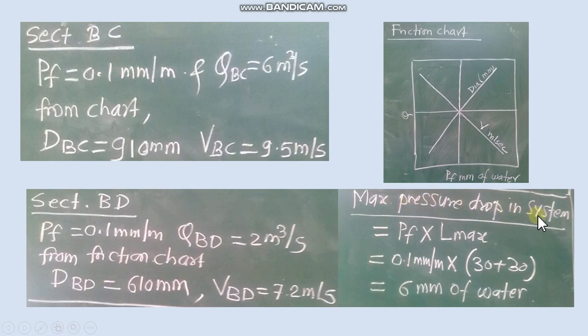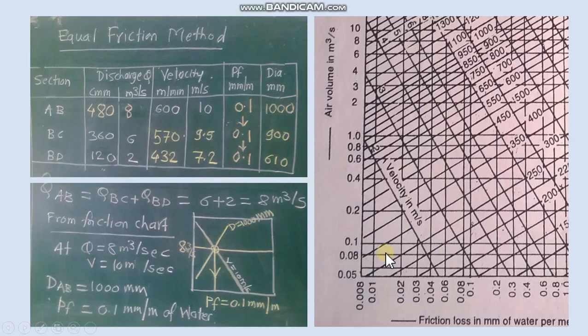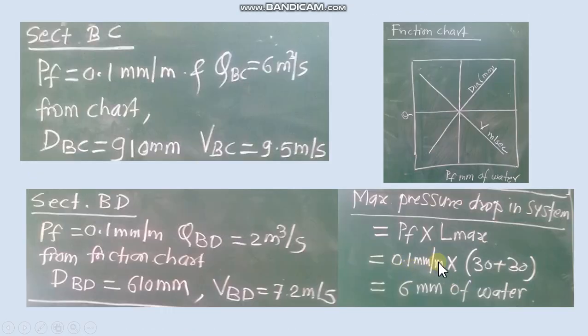Now maximum pressure drop in a system is a product of PF and maximum length. So here maximum length is 30 plus 10 is 40 meter and 30 plus 30 is 60 meter. So 60 meter is maximum length. We will take for the calculation and we calculate maximum pressure drop in the system.